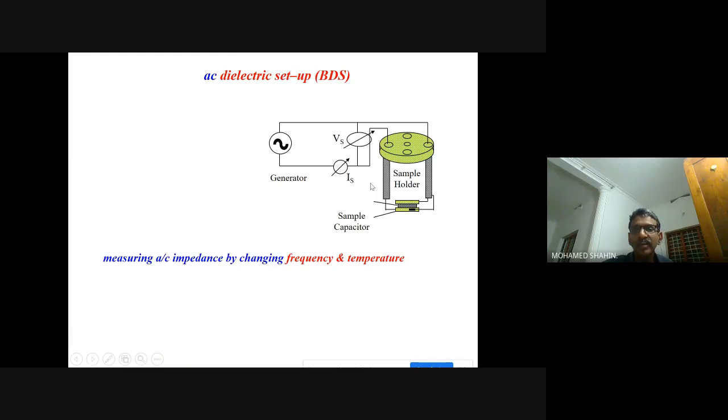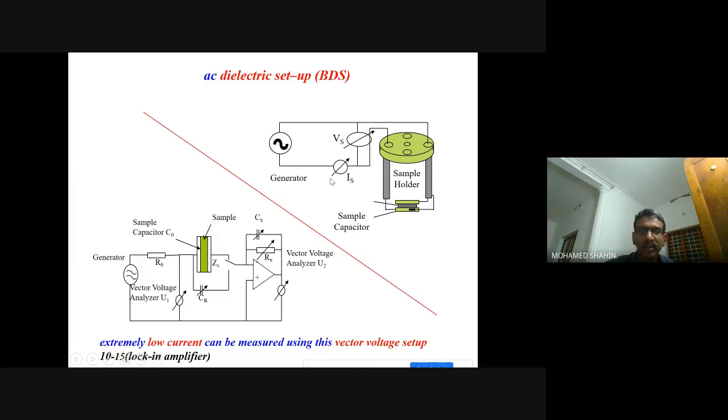The second thing, in an impedance measurement, you will be giving a voltage and the current is taken. So it does it like this. Before taking the sample, it takes a reference measurement. How does it take the reference measurement? This key, or this switch, would be touching this side, so that by the same volt you are standardizing your instrument by taking a standard capacitor.